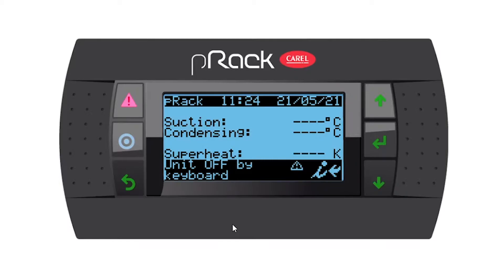In this video I'd like to show you how to set up a thermostat's generic function. For this exercise we're going to set up the generic function to act as a plant room cooling — we're going to open up a solenoid to assist in cooling down the plant room, so the P-rack can control the racks as well as act as an additional plant room cooling controller.